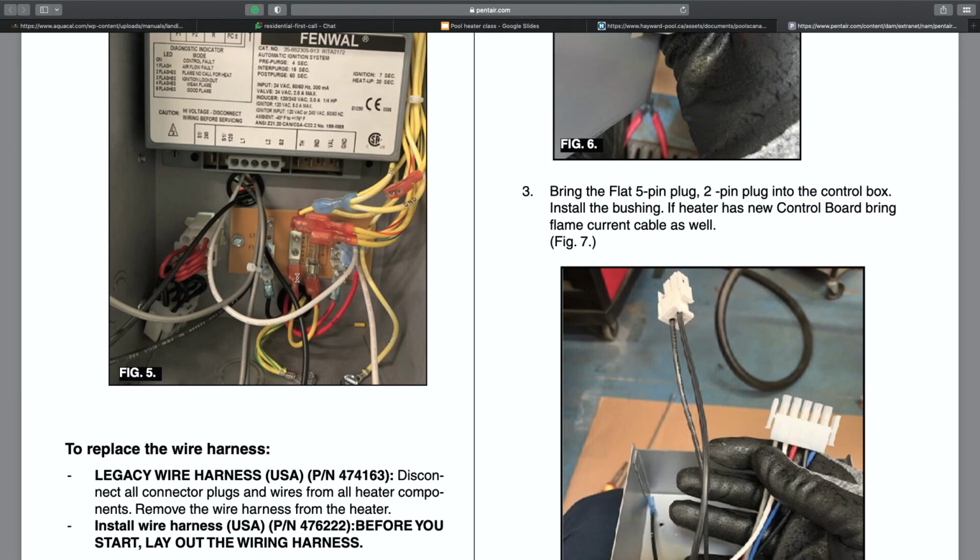So in this situation, you set your pool heater, you turn everything on at the display, and you set it for its max temperature, say 104. And then the 2-wire control system that has its own thermostat hooks into where these 2 yellows are. So if it closes, the display comes on for the heater and it runs. If it's not closed, depending how smart the heater is, it'll either pull an error code that we have a fuse open, because it's connected right here with the fuse, or there'll just be no display on the board.